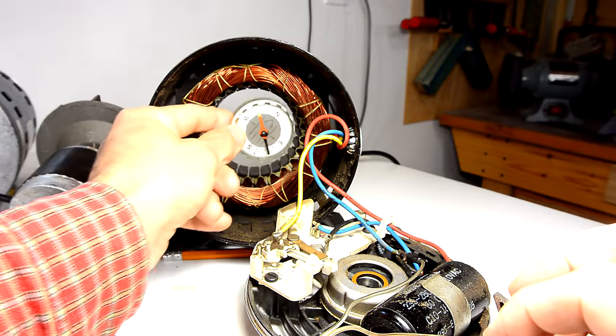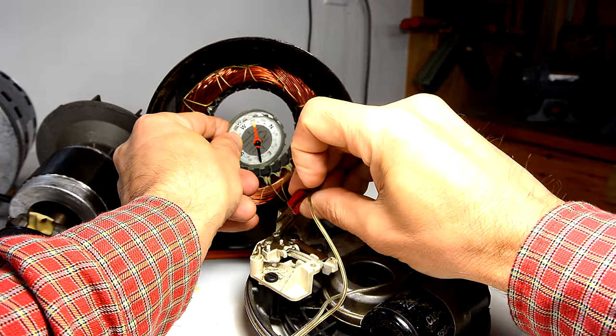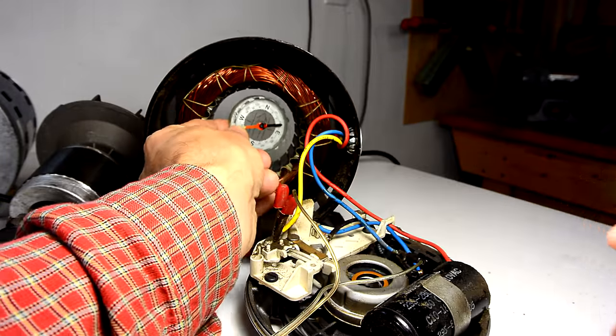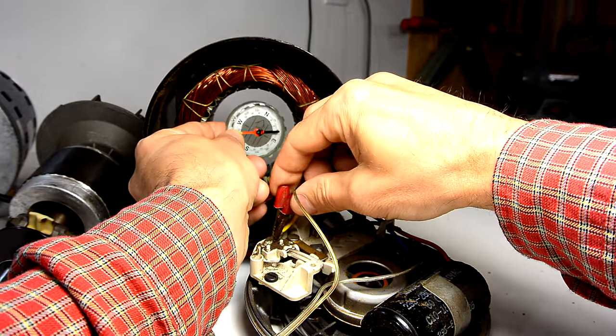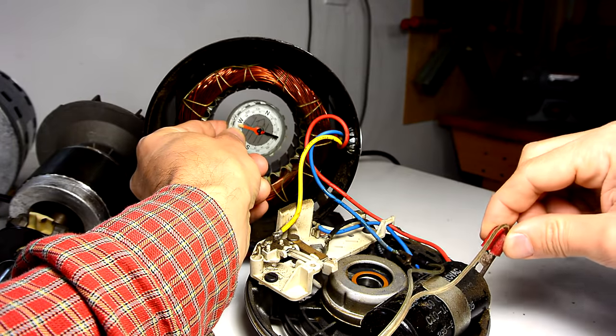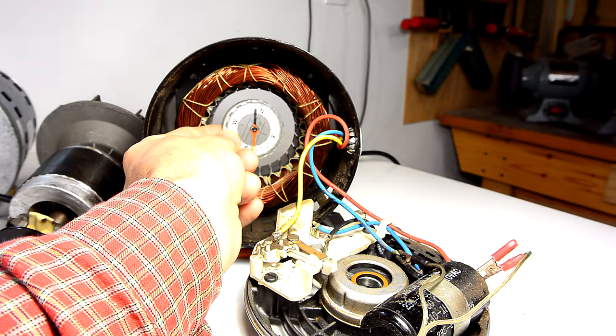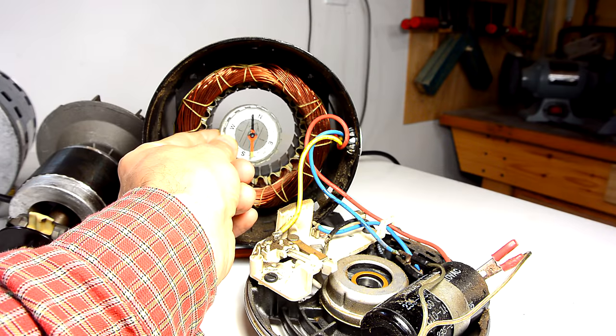Now if I put a compass in here and I put DC through the main winding you can see we have a horizontal magnetic field. And if I move that clip to activate the starter winding you can see we have a vertical magnetic field. So those windings are 90 degrees out of phase with each other.